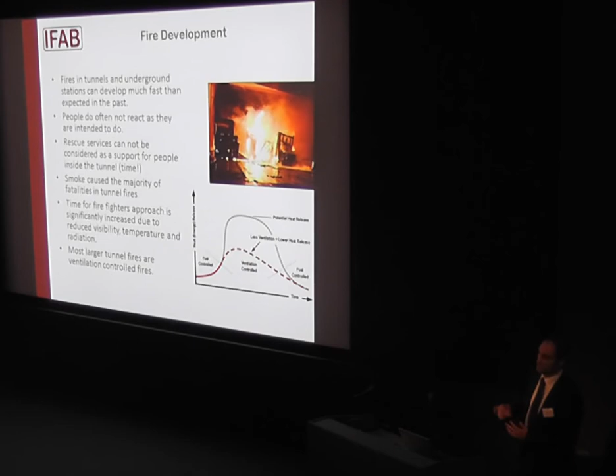So we have two major enemies inside tunnels. The one enemy is trucks, heavy goods vehicles. We don't know what is loaded on the trucks, and if they start to burn - which happens quite often, by the way, for technical reasons - then in most cases we have a fire between 30 and 100 megawatts, and in worst cases it can go up to 200, 250 megawatts. Of course then we are fully into the ventilation-controlled fire regime.